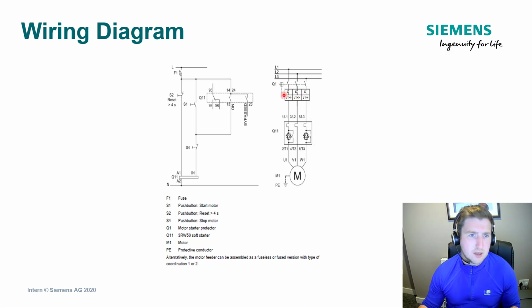If you go for type 2 coordination, the soft starter won't be compromised, and all you have to do is change the short circuit protection, and that's typically fuses. So the idea is that if you've got a soft starter which is rated at say 315 kilowatts, that's quite a high value item. You'd probably go with type 2 coordination. Whereas if you've got a low value 5.5 kilowatt soft starter, you might opt for a 3RV motor starter protector because you've got to weigh up the costs.